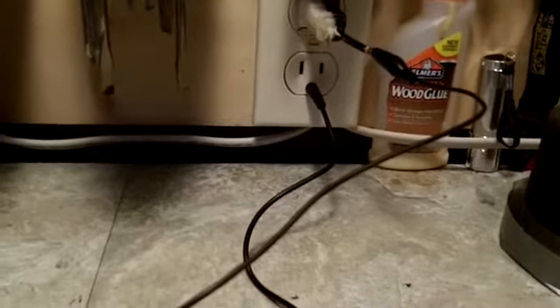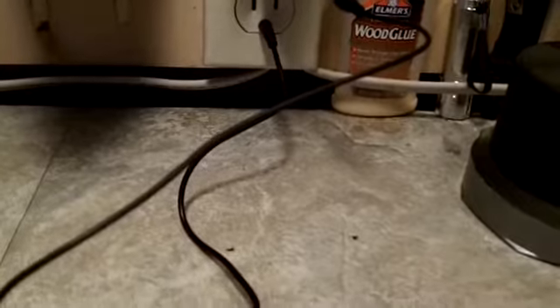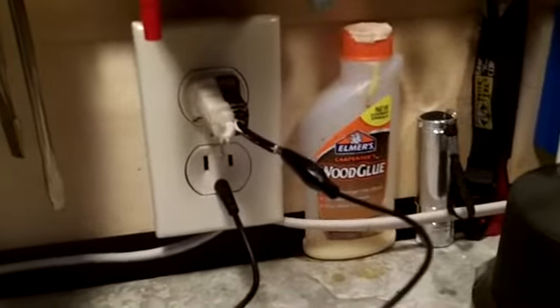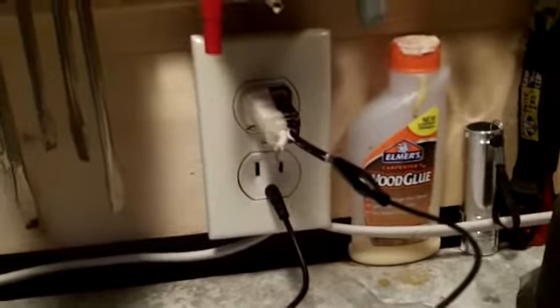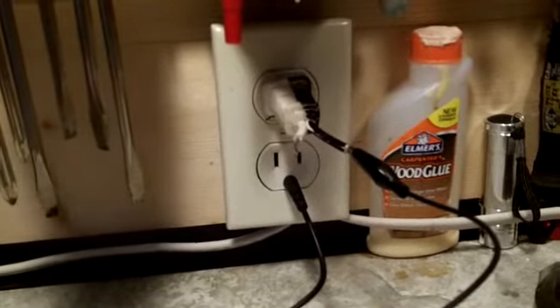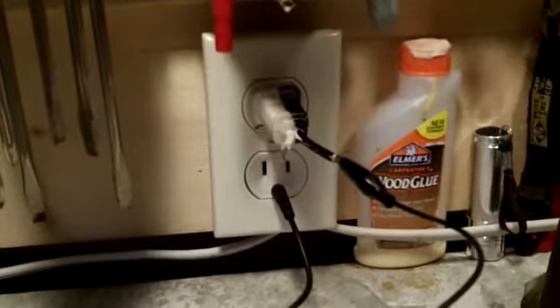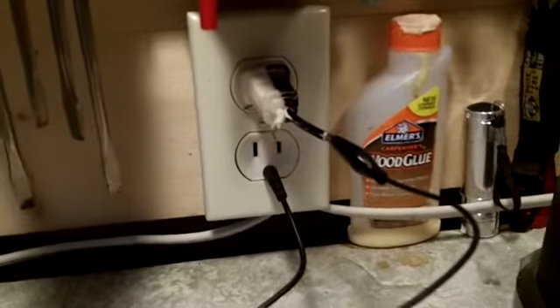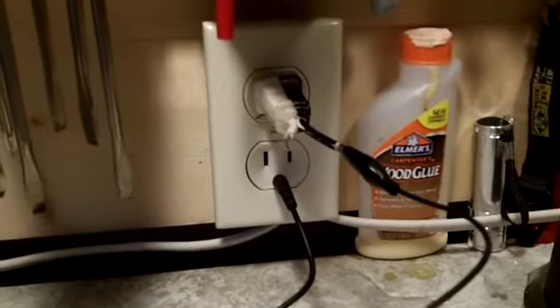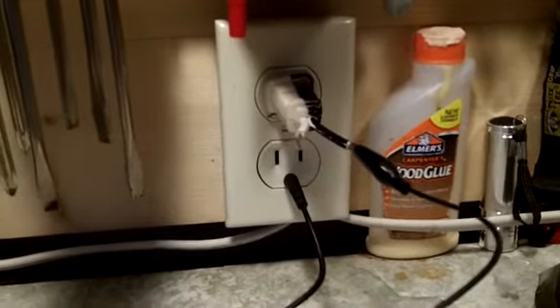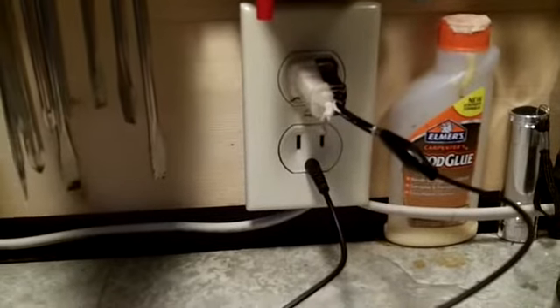I should say it lessens the shock potential, so that if you come in contact with something grounded, like if I was barefooted with a wet floor, my feet would be grounded, and if I touched that hot wire, I could get a severe shock or even death. That's the idea I want to prevent. I don't want to plug in anything and get an earth ground path back to earth ground, because that's just the way it works.